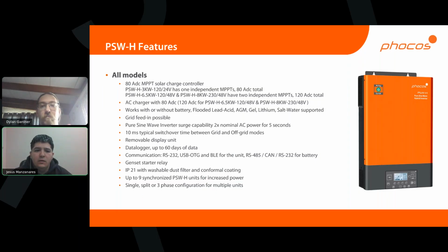It works with or without battery. We mainly recommend having a battery for the system at all times. That is our recommendation. It works with flooded lead acid, AGM, gel, as well as lithium batteries. It is fully customizable to the battery specs within our settings. It does 2 times nominal for 5 seconds. If it is accepted in your region, you can also do a grid feed. It communicates through RS-232 for the battery. It does RS-485 and can also do communication on lithium batteries between the inverter and the battery system.